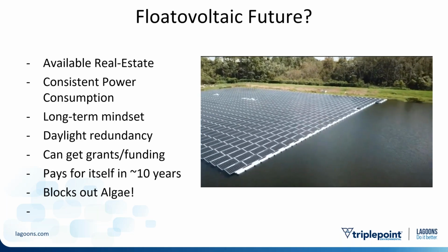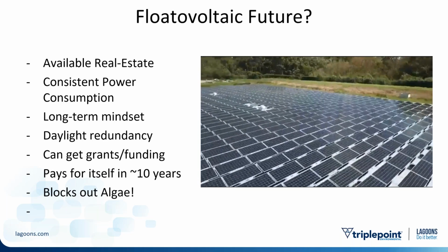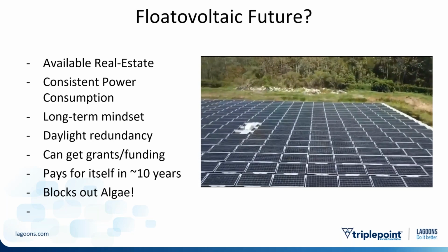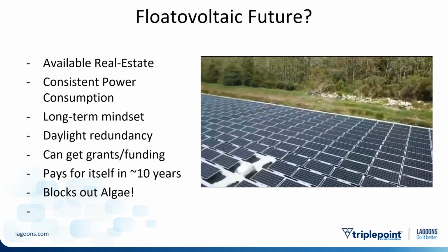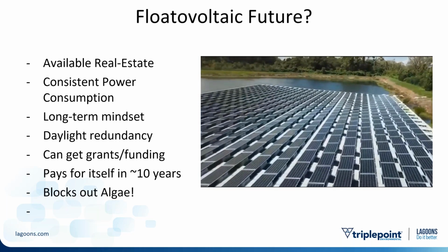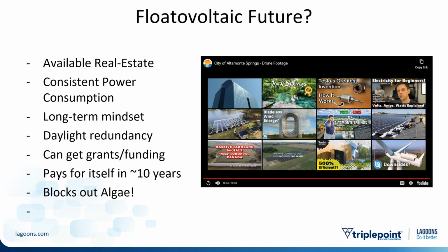Lagoon systems can benefit from this because if the power were to go out in the middle of the day, you've got redundancy such that you can run your aeration system. And there are incentives, depending on the different utility in parts of the country or different states, you can get grants or funding for this kind of initiative. Our understanding is that solar generally pays for itself in about 10 years, which is well before the lifespan of a 20-year project. And another cool factor is it's a de facto cover.